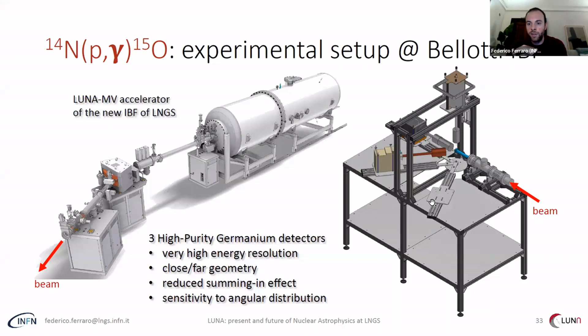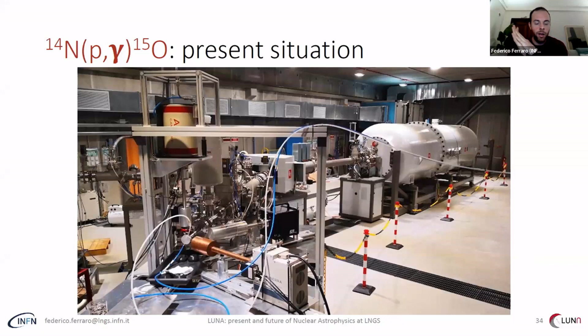And this is how the setup actually looks. This is a picture that I took today. So here you see the accelerator. The beam is going out of the accelerator, coming into this tube. Here is the magnet that basically decides where the beam should go, into this beamline or the other. Well, we would like the beam to go into this beamline for this reaction, and the beam reaches the target that is sitting here. And you see these tubes. These are for the cooling water that we use to cool down the target itself while the beam heats it up. And all around you see this germanium detector here, which always stands at 90 degrees with respect to the beam direction, and these other 2 that are able to change the angle with respect to the beam axis, and to also change the distance from the target so that we can study the summing-in and angular distribution effects.